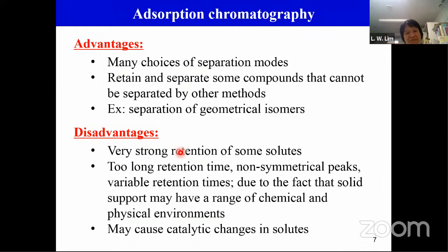Some students asked what happens when there's a peak, like an overlapping peak. And sometimes you have a peak which is asymmetric, like a broad peak. So usually when you have a column flow like this, sometimes when the column is old, you need to wash the column. But sometimes you need to open the column and fill a little bit on top of here. So, sorry.